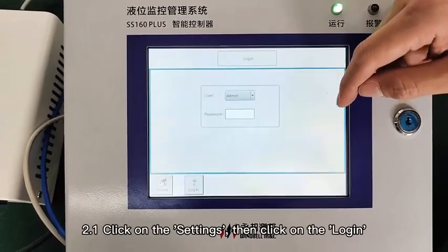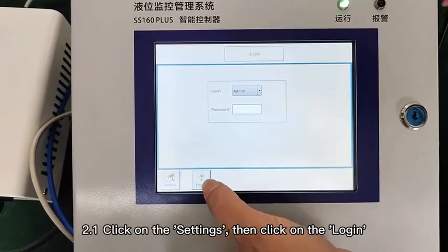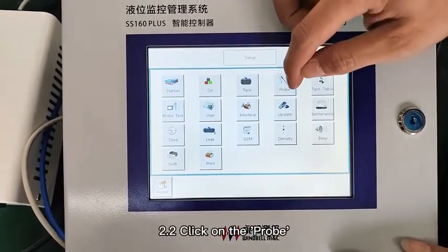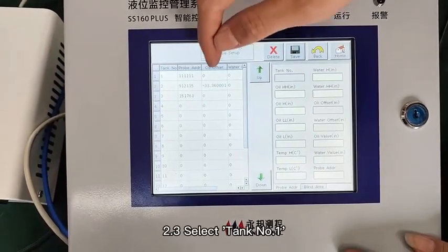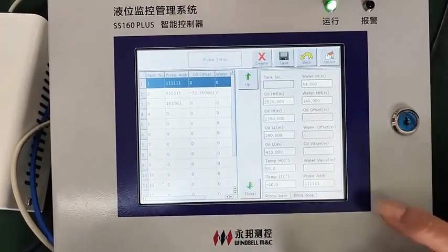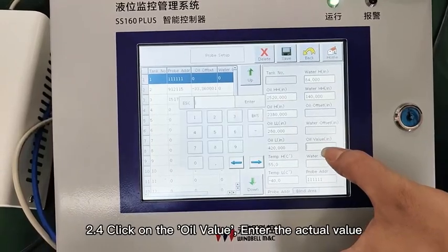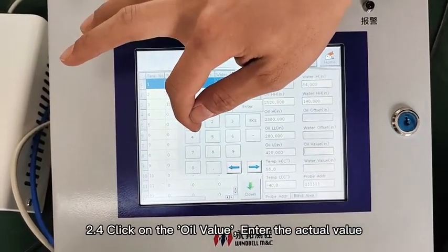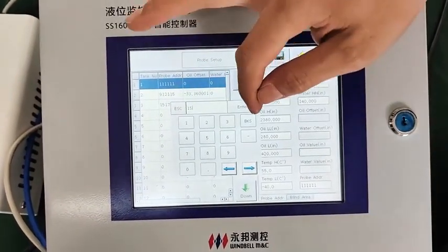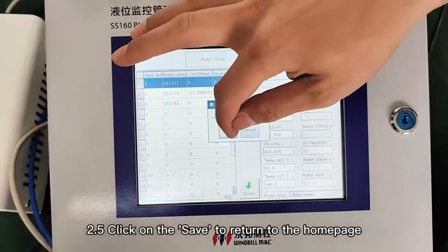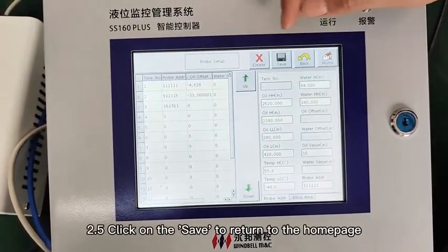Part 2. SS160 Plus console setting of calibration tank. 1. Click on Settings, then click on Login. 2. Click on Probe. 3. Select tank number 1. 4. Click on oil value, enter the actual value. 5. Click on Save to return to the home page.